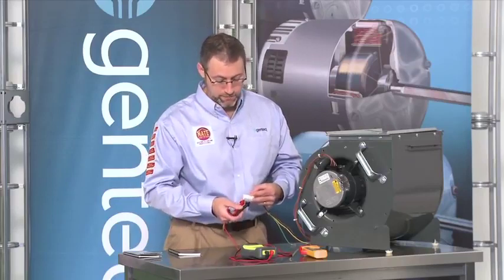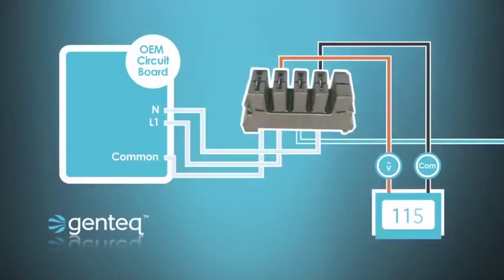We would then check from line 1 to neutral on a 115 volt system and confirm that we have 115 volts. If we do not have 115 volts, we would have to follow these wires back to the manufacturer's control board and find out where we lost that power. So really, that is going to be the same check no matter what voltage the motor operates at. If it's a 230 volt or a 460 volt motor, we're still going to make the same check.